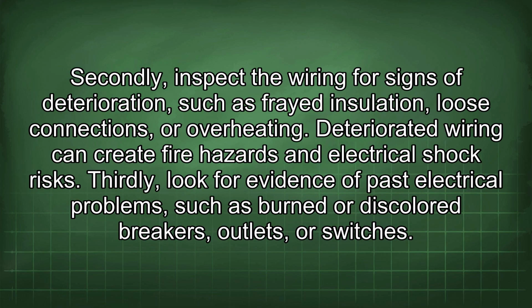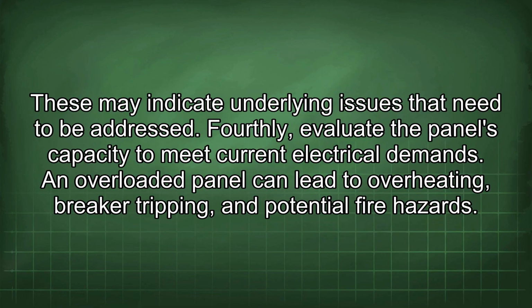Secondly, inspect the wiring for signs of deterioration, such as frayed insulation, loose connections, or overheating. Deteriorated wiring can create fire hazards and electrical shock risks. Thirdly, look for evidence of past electrical problems, such as burned or discolored breakers, outlets, or switches. These may indicate underlying issues that need to be addressed. Fourthly, evaluate the panel's capacity to meet current electrical demands. An overloaded panel can lead to overheating, breaker tripping, and potential fire hazards.